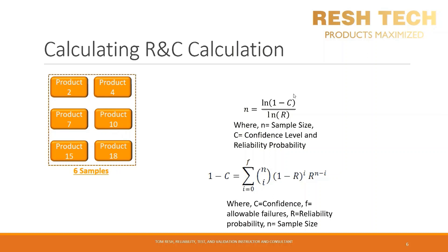The math behind LTPD and reliability and confidence sampling calculations when considering allowable failures is very similar. The key difference is the specific definitions and presentation of the values — where LTPD is the percentage of failures that will be detected and rejected, and reliability is the percentage of the population which will perform at a specific condition during the lifetime of the product in the field. For this example, we are going to take the six samples selected from the population and calculate the reliability based on a 90% confidence level, which is the standard value used for reliability and confidence and LTPD sampling plans.